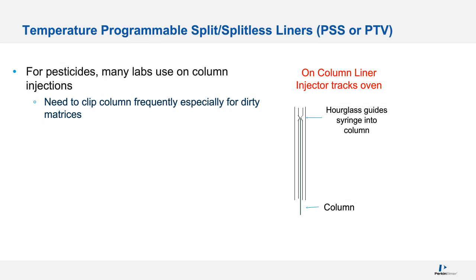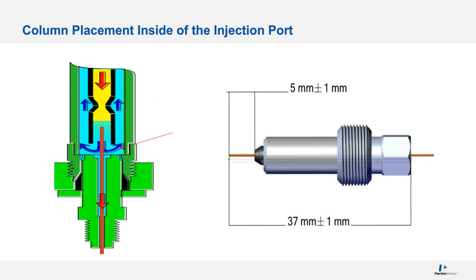The other thing that's critical is the placement of the column in the injector port. Vendors do not do this to be mean. If the column is too far into that liner, the sample may not go in the column, but outside of the column, and the recovery would be poor. So the placement of the column enhances recovery. It also prevents carryover as ghost peaks, because then the targets in the next injection could get into the column and cause other issues.